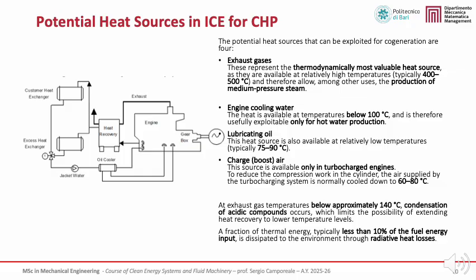In ICE-based CHP systems, there are four main sources of recoverable thermal energy. The most important heat source is represented by the exhaust gases. These constitute the thermodynamically most valuable heat stream because they are available at relatively high temperatures, typically between 400 and 500 degrees Celsius. As a result, exhaust heat can be used not only for hot water production, but also for the generation of medium pressure steam when required by the application.